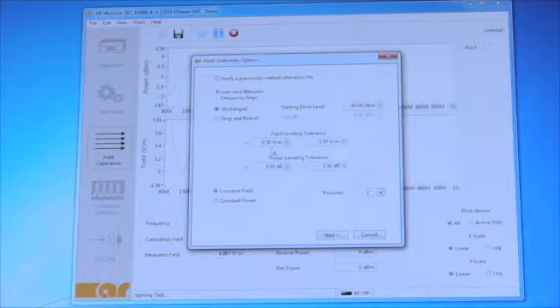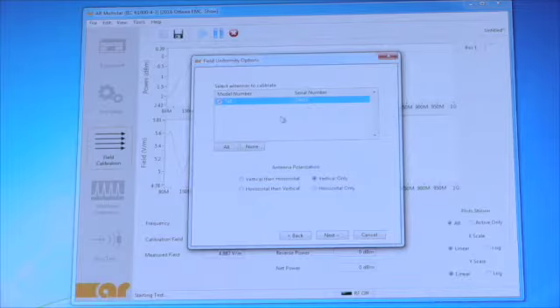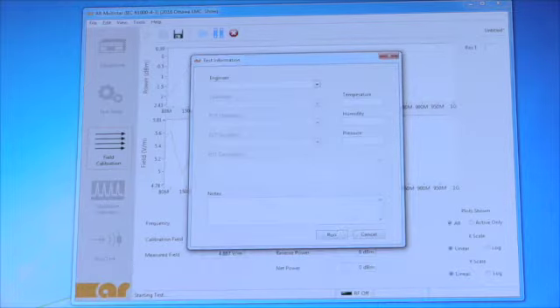Right. So once you have that all set, and then my positions, here I can put 1 position up to 20 positions. I know the IEC standard recommends 16 positions there. Once you have that parameter, here's where you can select your antenna. In this case, I'm just going to do vertical, but you can do vertical then horizontal, or horizontal and vertical. So it gives you a choice of what order you want to select the antenna. Once you have this, this is test information for the test report. So you can input all that and hit run.